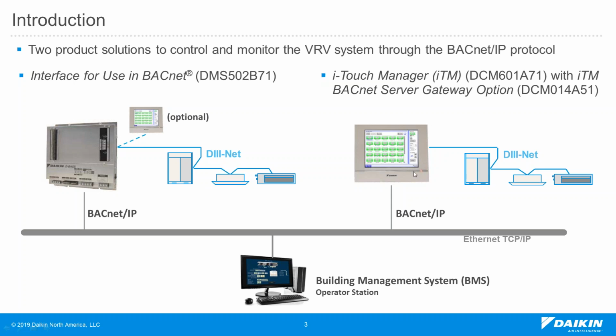The second solution is the ITM BACnet Server Gateway. It is a software option to the iTouch Manager. It helps the ITM to be not only a central controller to control the VRV system, but also a gateway to integrate with the BMS, and it eliminates the need for an actual hardware gateway.